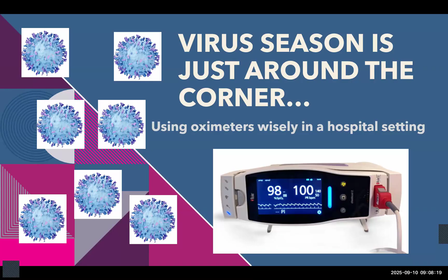So, a couple of basic principles of the pulse oximeters. Number one is pulse oximeters lie. If you have motion artifact, you will not get an accurate reading. So first of all, always ignore the O2 sat if the child is coughing, crying, pooping, eating, vomiting. There will always be motion artifact. It really doesn't matter whether the O2 sat is 85 or 25. The number doesn't mean anything. If the display doesn't fit with your clinical impression, make sure the probe is on properly. Sometimes we reuse those Band-Aid probes for weeks and they get dirty and grungy and they're not accurate. Get a new probe put on. Make sure that the light emitter and the sensor are exactly opposite each other.